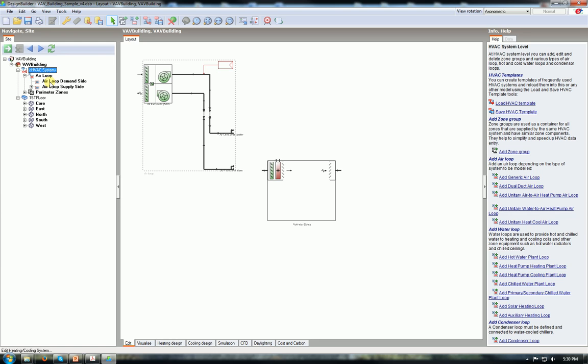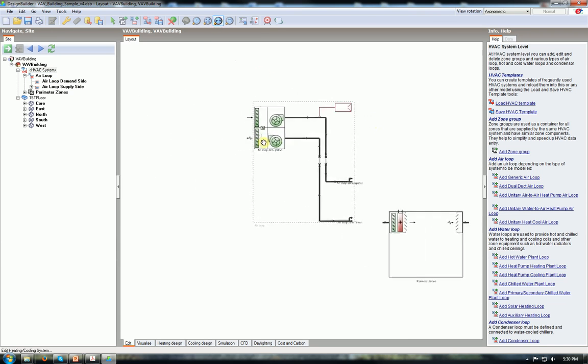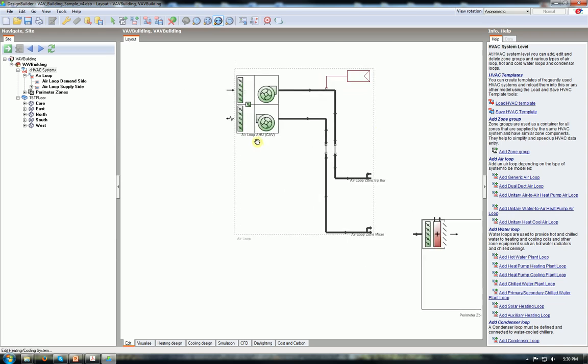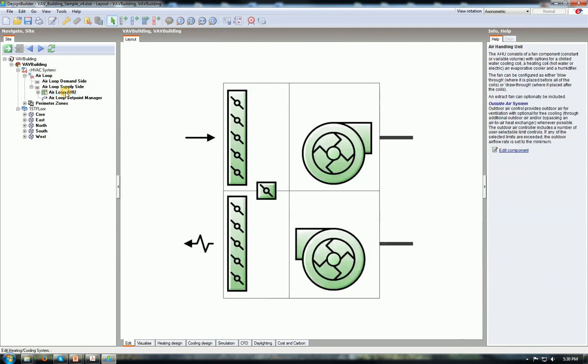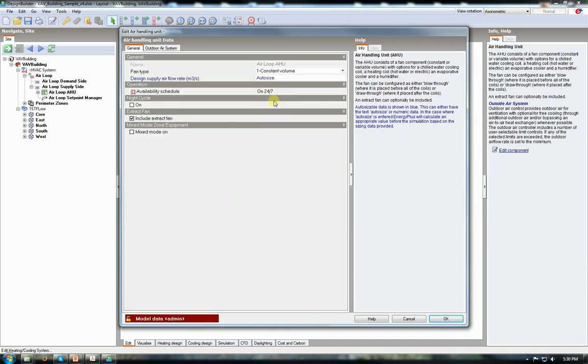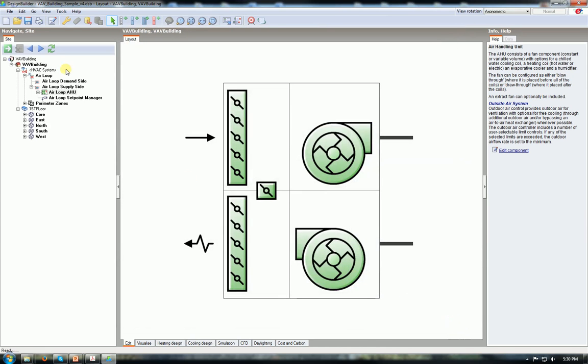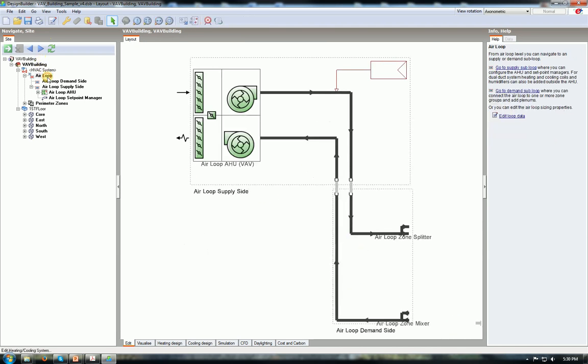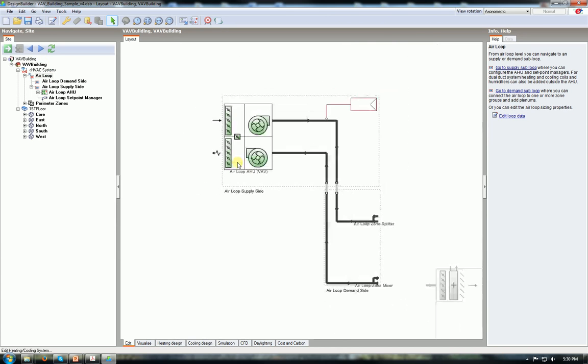It has demand side and supply side and all the equipments. Put aside, zoom in a little bit. And we see its type is CAV. But we are trying to create a VAV system. So there is a problem. We need to correct it. Go to the air loop AHU, click, edit, right click. And you see this fan type is constant volume. Change it to variable volume. It's type 2. Say okay. It will be changed to variable volume. And then go to the air loop. Zoom a little bit. And you see air loop VAV. The problem is solved. So we can continue.